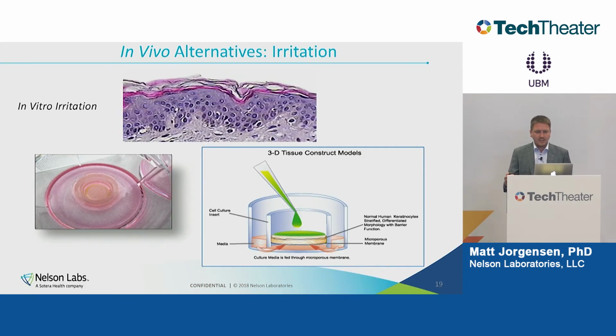One of the ways things are changing is that we have some new in vivo alternatives to common and very popular tests. Irritation testing is one of what we call the big three. If you look in the 10993-1 and the FDA guidance, this is required for all devices. Traditionally, the irritation test is an animal test with rabbits, where you would essentially either put a device or an extract from a device onto rabbit skin and see if it gives them a rash.